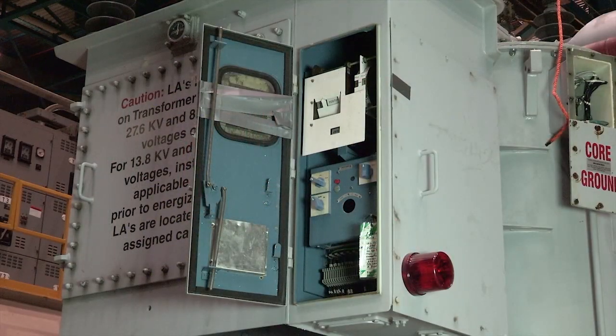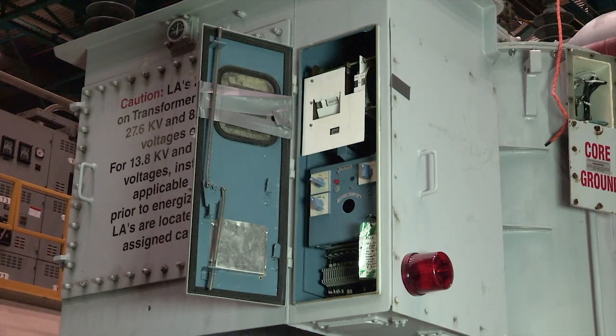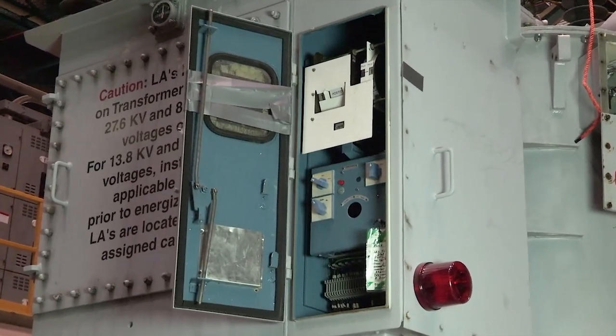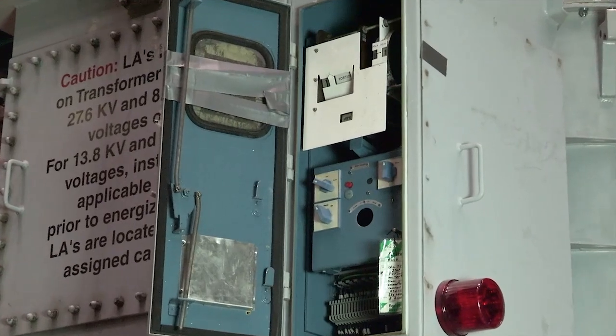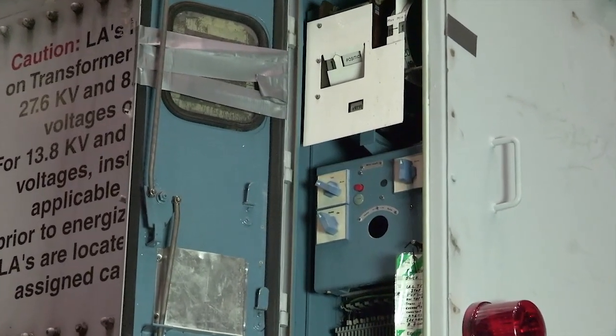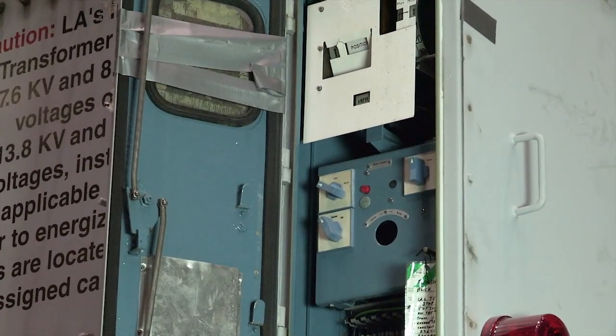All right, we have the ULTC control mech cabinet. What do you want to do? We talked a little bit earlier about operating electronically to its limits, even manually, to make sure it's not binding or anything like that. Make sure the counter's working. The heater also in that control mech is something to check for. And just make sure the position gauge is moving and your limits are indicated at max and minimum. And that duct tape there you see too, it's always good practice to throw some gasket material over the glass so it doesn't break from rocks down the road.